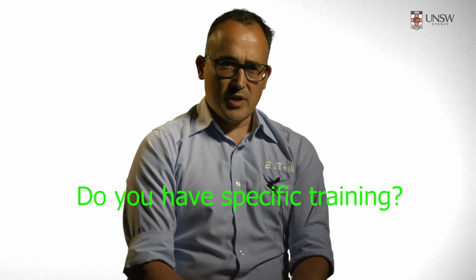Due to that, we've had a number of instances recently where unqualified personnel or contractors who are unfamiliar with batteries within the UPS system have worked on the equipment, and they've shorted out the batteries and injured themselves. Within Eaton itself, we train our service technicians, particularly on how to work on batteries and how to mitigate the risk of injuring themselves or causing an incident on the batteries. Externally, we provide documentation with our UPS systems for electricians on how to work on the batteries, as well as signage on the systems alerting them to the arc flash risk.